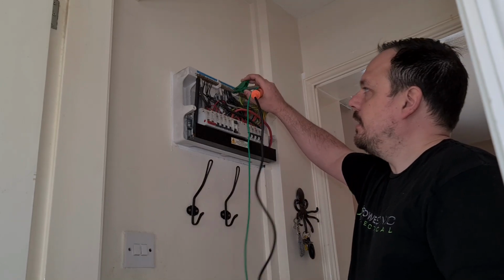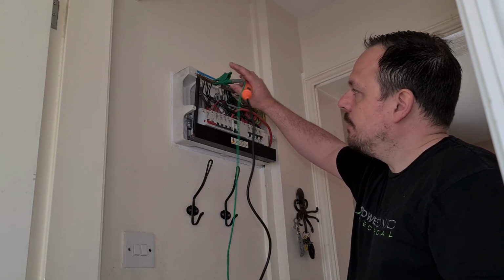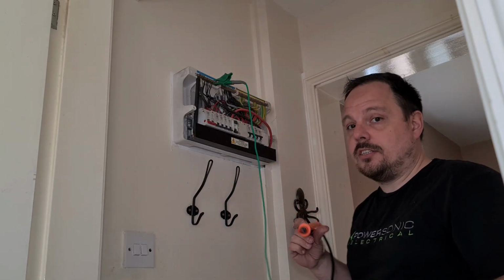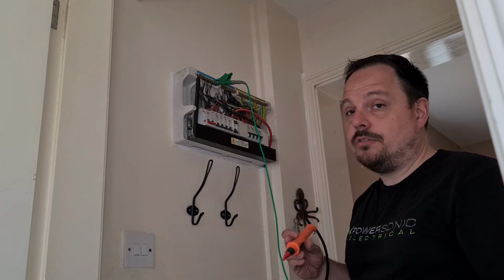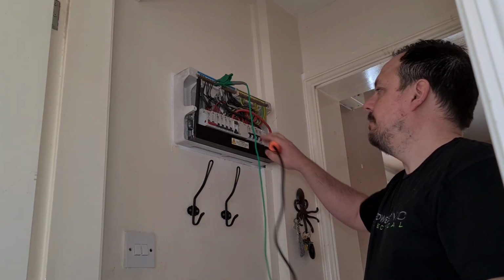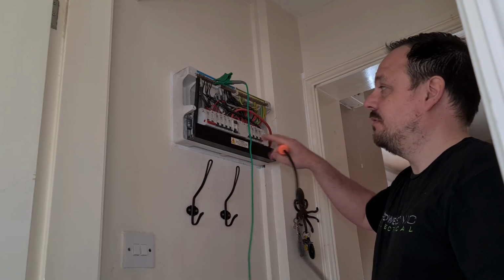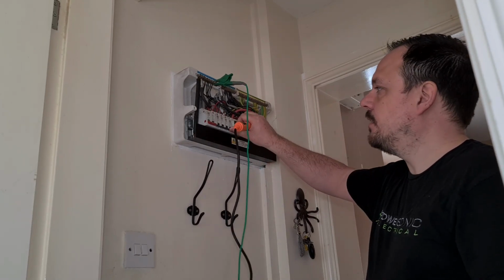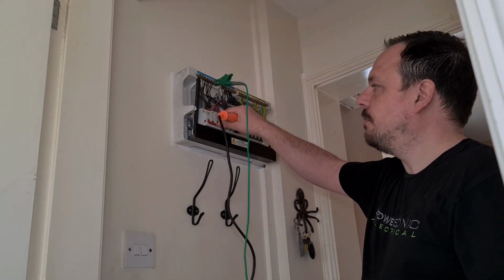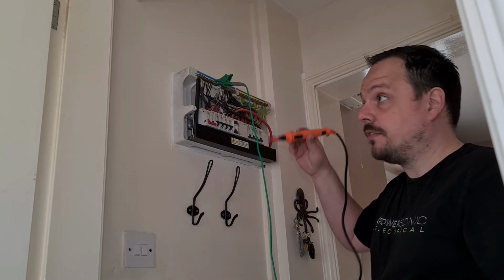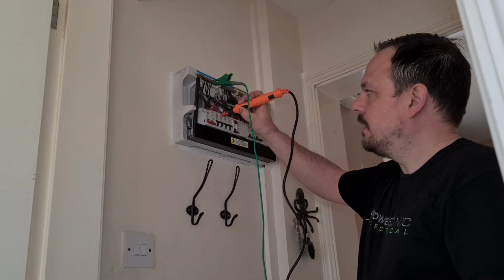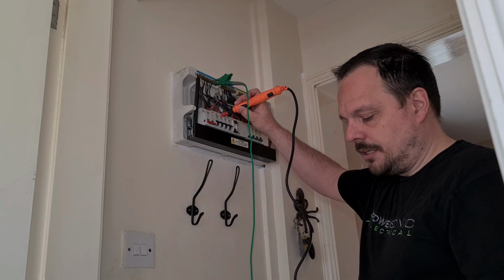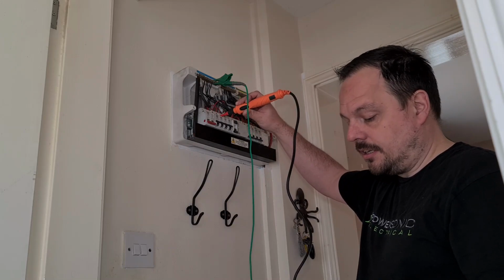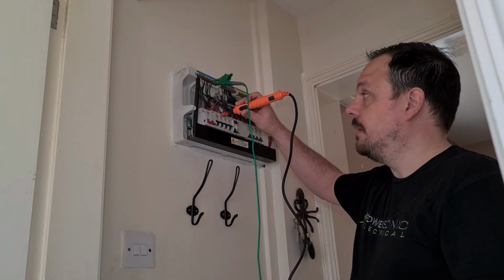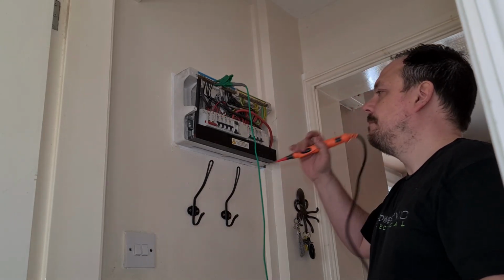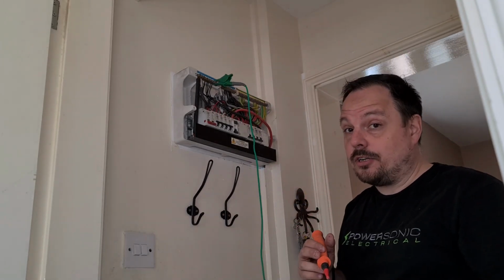Now if I am to repeat that, for example, on this side where we know that there is lighting connected in circuit, we'll keep it at 250 volts. And if I turn, doesn't really matter because the RCD is off, but we turn all these lighting MCBs into the on position, we can test all of those at once as well. Now this should be a very low number because I know there's equipment connected in the circuit, and it is, it's 0.02 megohms. So that's kind of what you would expect.